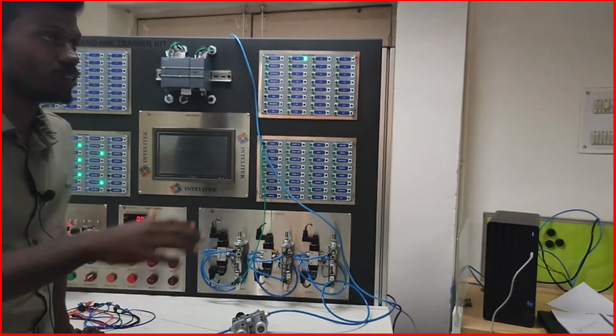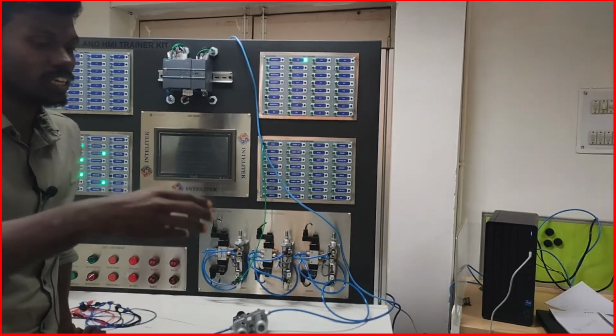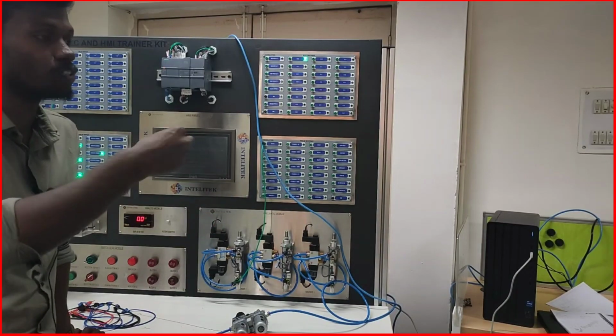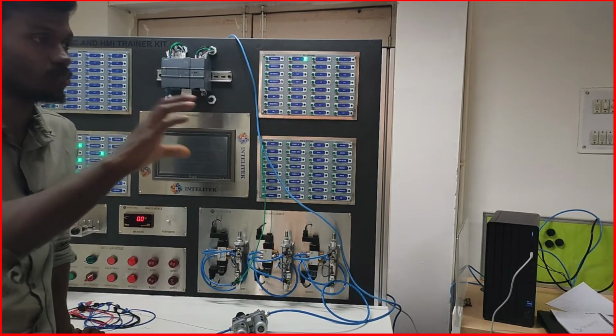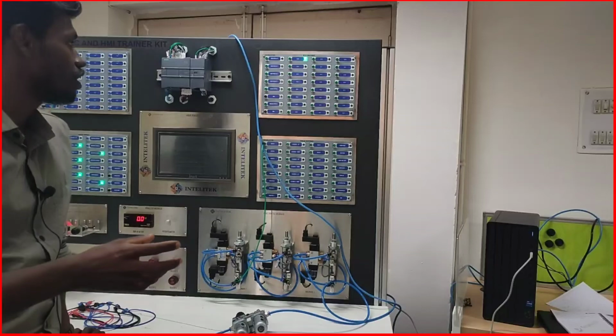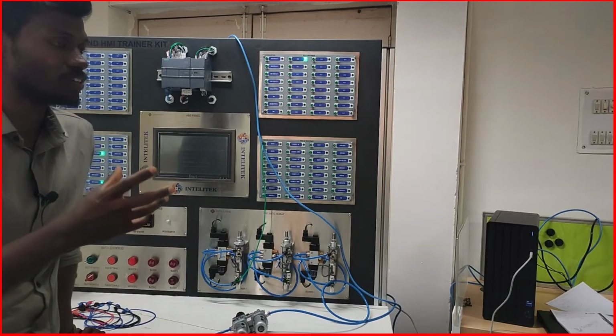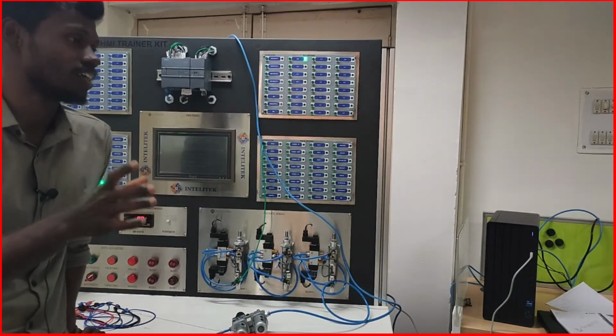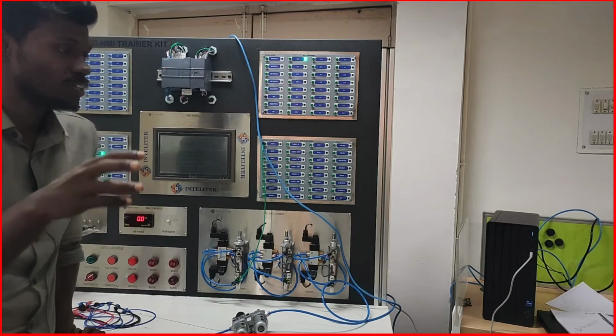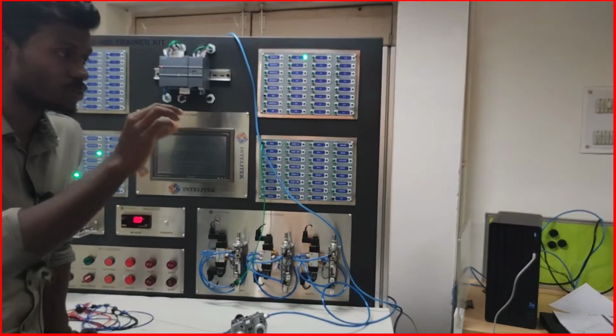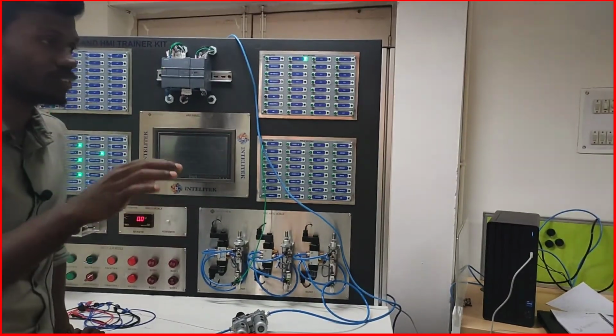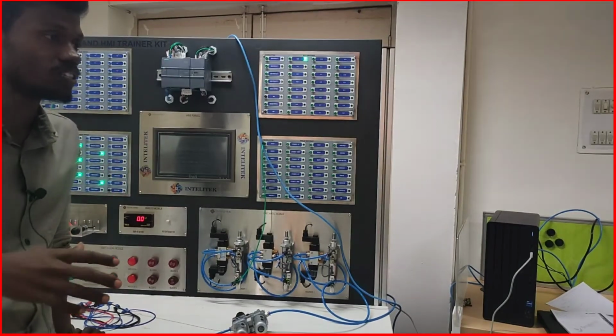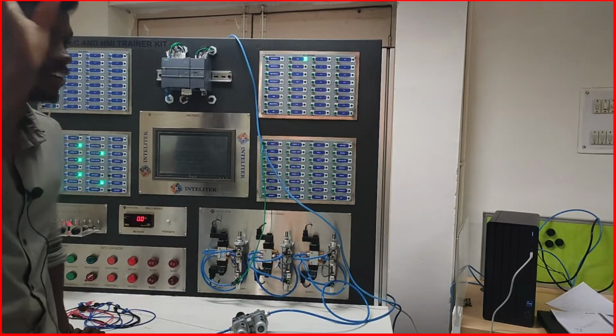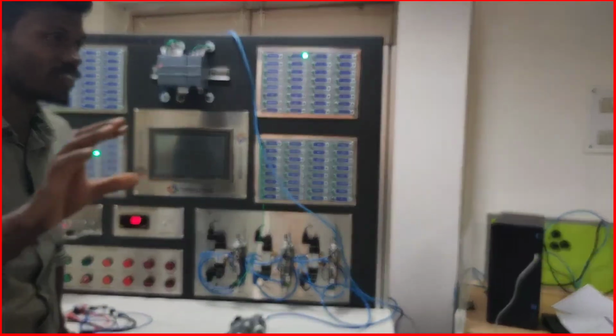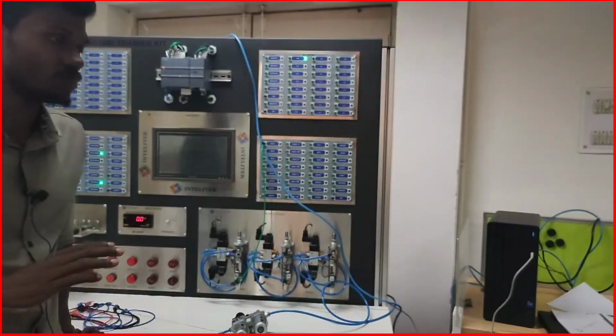These sensors' outputs are all connected to small controllers. In BMS, Siemens calls them DDC controllers, direct digital controllers. So those controllers are connected to small systems at a small level, just to control this thing. We don't need to go to PLC levels and all, just small DDC controllers are enough to control this room.